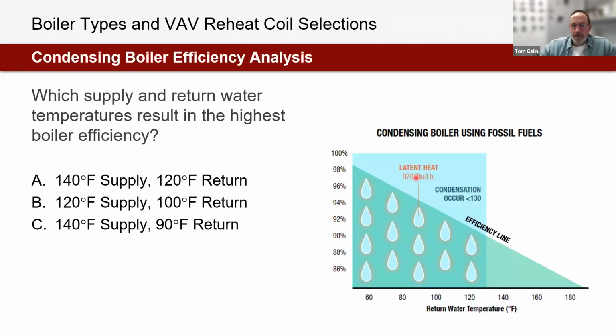And that's really fun because often we end up in resubmittal mode on these jobs where we're trying to get the BTUs out of the heating coil, and at the same time the engineer's saying that's all great, but you can't go below 120 degrees. Well, we can't get you the BTUs, so we'll tell you what, solve for capacity or solve for something else, but it's all the same, and we just can't get the heat out of it if the temperature off the coil isn't. Well, and the truth is, once we've assumed a 20-degree delta T, that's going to influence the total GPM for the building we're assuming. It's going to influence valve sizing, distribution, piping. That could even influence, depending on the scope of the project, the nature and the way that we actually insulate pipe.